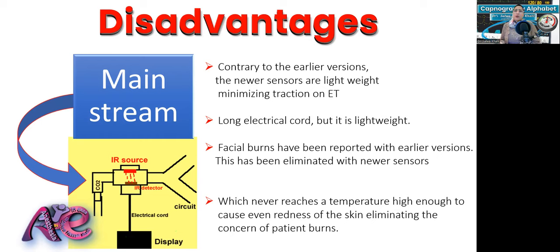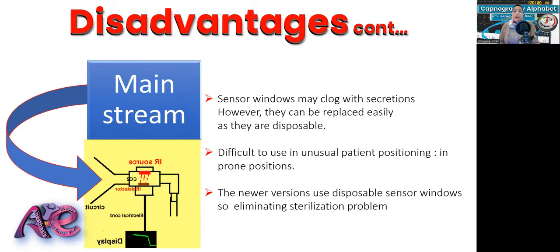Earlier mainstream capnography versions reported facial burns due to overheating of the airway adapter needed to prevent water vapor condensation; new sensors never reach temperatures high enough to cause even skin redness. The sensor window may clog with secretions, but these are disposable and easily replaced. Mainstream capnography is more difficult to use in unusual positioning such as prone position compared to sidestream. The new version uses disposable sensor windows, eliminating sterilization concerns.